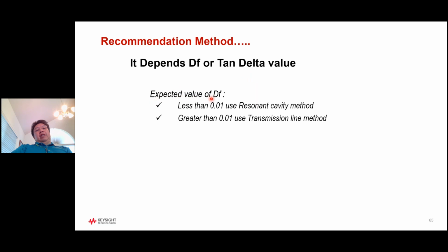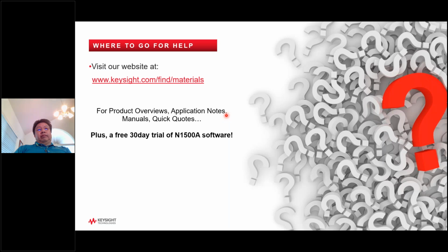So if you expect the DF, or your quality factor tan delta value, to be less than 0.01, use the resonant cavity method. This is the only method that's available for low loss material, and it gives you enough measurement resolution to get this type of accuracy. If it is greater than 0.01, then you can use the transmission line method or coaxial method. This method will not give you accurate enough measurement resolution if you have really low loss materials.